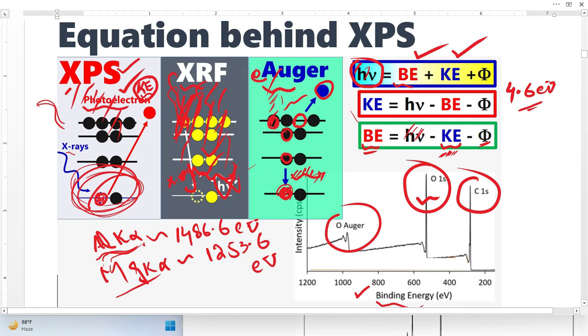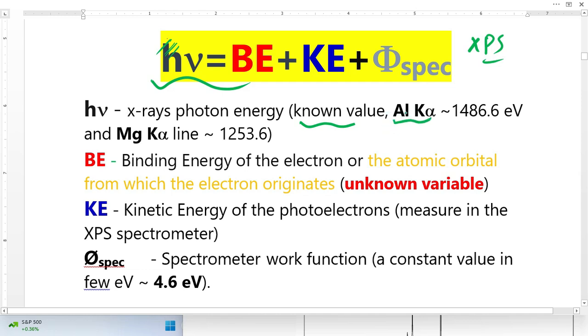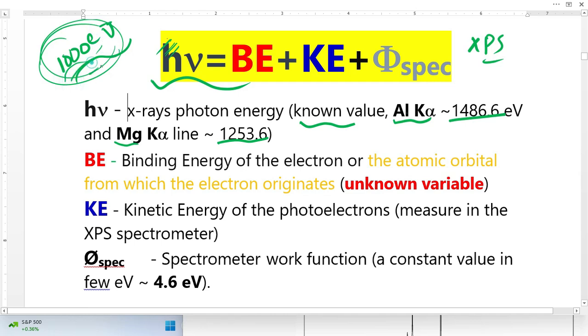Let's discuss this fundamental equation behind XPS in detail. This is basically the photon energy — the X-ray photon energy — which is a known value. In XPS we use two types of sources: one from aluminum with energy 1486.6 eV, and one from magnesium. We use these because most elements have binding energies in the range of up to 1000 eV, so we need at least this much X-ray energy or more.